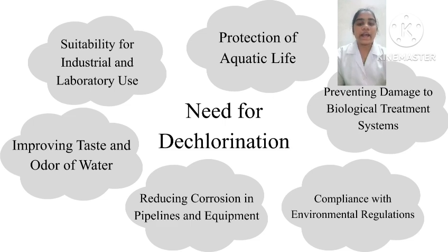Second, prevent damage to the biological treatment system. The residual chlorine can kill the beneficial microorganisms in biological wastewater treatment units. Dechlorination helps to maintain proper microbial activity. Third, compliance with environmental regulations. Many discharge standards limit the residual chlorine. Dechlorination ensures the treated water meets them.